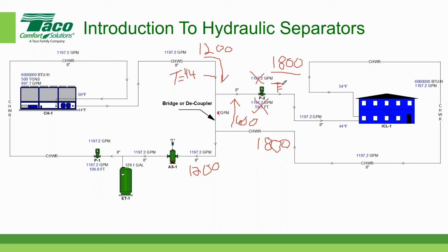But this temperature over here is now going to be a mix. Let's assume that it starts off, again, we'll just assume that this is 56 here. Let's X that out. If this is 56, now the return water temperature is 56, goes in at 44, comes back at 56. But since that 56 is flowing in the opposite direction, it's going to turn out to be halfway between these two values here. So in other words, the return water temperature is now going to be, instead of 44, 50 degrees Fahrenheit. Has anybody typed that in? Yep. We got some 50s. Yep, 50 degrees.